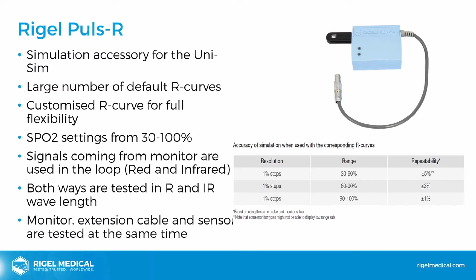We've got a table there, so we're looking at repeatability, not accuracy. Is one thing to take note. We improve the repeatability of SpO2 testing by having these manufacturer specific R curves. If anyone's missed the previous webinars where I spoke about R curves, this is available on our website, so please view that if R curves aren't particularly understood.